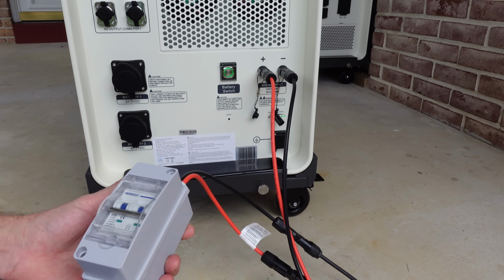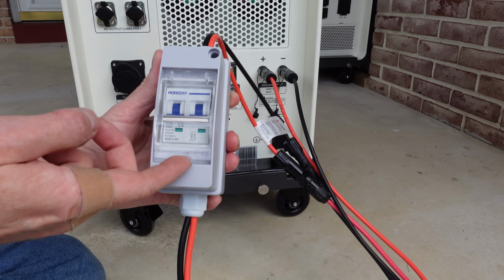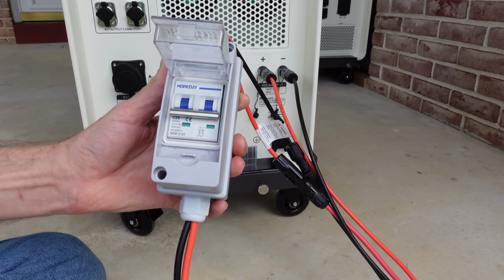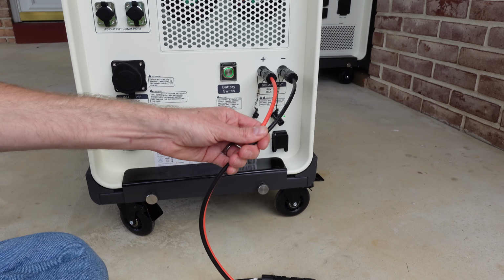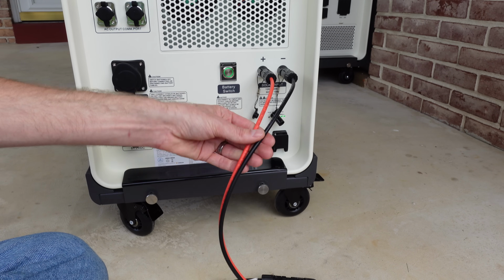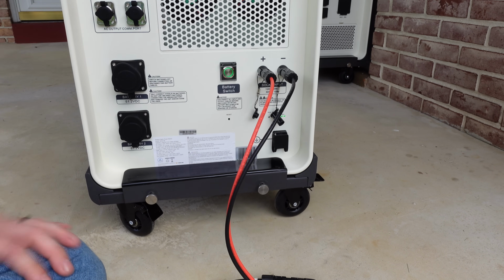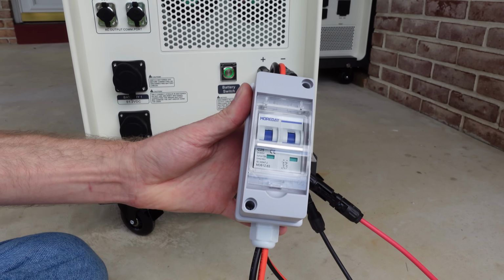When I'm ready to disconnect the solar panels, I'll make sure the circuit breaker is in the off position. It is disengaged. You do not want to disconnect these cables under load. The high DC voltage will result in arcing as soon as you remove them, so it is important to make sure your circuit breaker is shut off first.